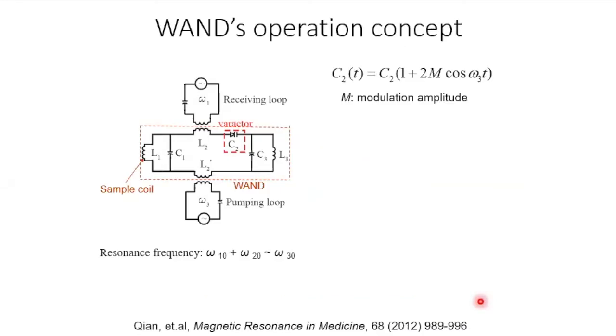So here's the detailed circuitry of the sensor. The nonlinear circuit, the first generation circuit, has 3 meshes. It's basically a triple frequency resonator, with one of its capacitors substituted by a nonlinear capacitor, which we call the varactor. And the resonator also couples with a receiving loop, which is just an ordinary NMR surface coil. And it is also inductively coupled with the pumping loop, which will provide the wireless energy to charge up the sensor.